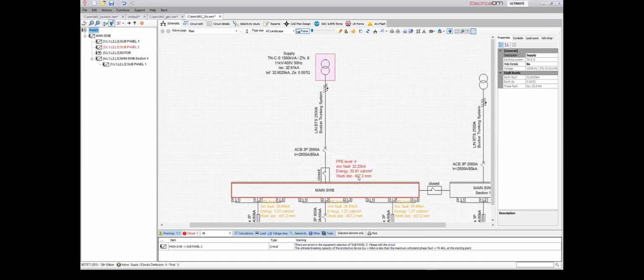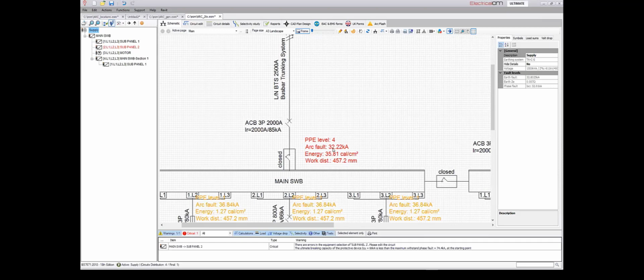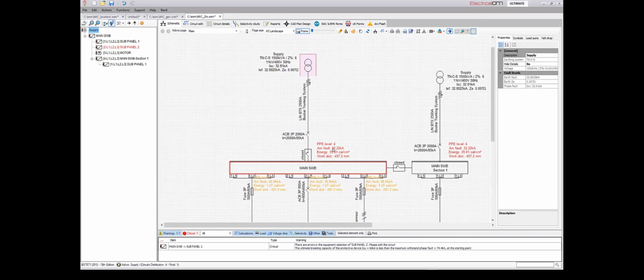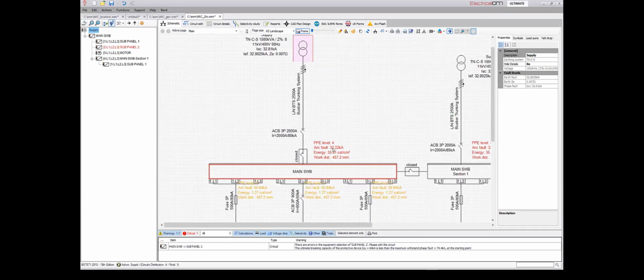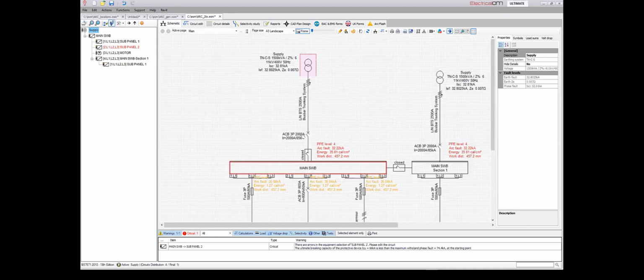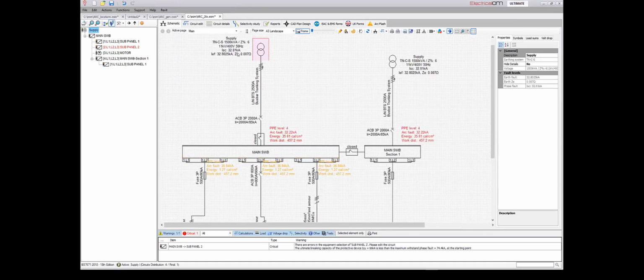And of course, the calculations will be refreshed, and we can see here that the arc fault usually is less than the normal fault level. You see that here in this case it is almost similar to the fault level of the source, meaning that there is a contribution from this source to this fault level here.